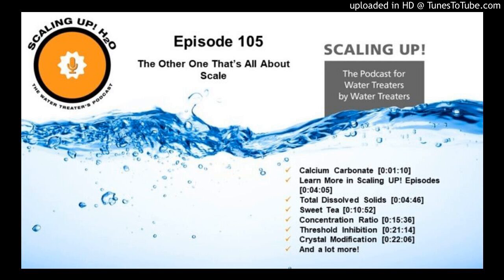Now, I did say non-scaling. I did not say how corrosive the water is, because Nation, all water is corrosive. So when we say it's either scaling or corrosive, that's not a correct way of saying that. Water's the universal solvent. It only knows how to do one thing, and that is to dissolve, i.e. corrode. So we know that waters are either scaling or non-scaling. They have one of those tendencies. So the 5 things that create calcium carbonate are the 5 things that go into the scaling indices. Those are alkalinity, hardness, pH, total dissolved solids, and temperature.